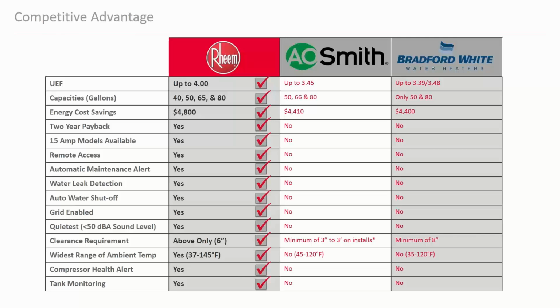It has the widest range of ambient temperatures. Up in Michigan, I know everybody talks about up north. They say, well, these heat pumps don't work up here. Well, this will. It'll go all the way down to 37 ambient and 145 on the top end. Most people in my area, if these go into a ranch home, they duct these things into the attic, pull that hot, humid air out in the summertime, cool it, and put it right back up in the attic. It helps keep the home cool, helps the efficiency of the home, and dehumidifies it.